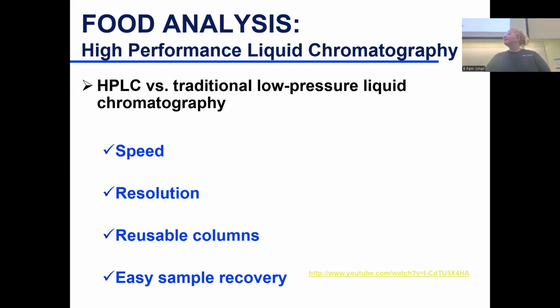Because I'm just thinking column chromatography right now for the other. Low pressure can connect to a detector as well, and a high end detector that can do the detection and analysis for you. Yeah, what I want to say is you can inject as low as 1 microliter, even if you have ultra pressure or ultra performance with very small columns, but you can inject up to 100 microliters or a little bit more on the big thick column, so it has better capacity, more capacity. This is the one you use.